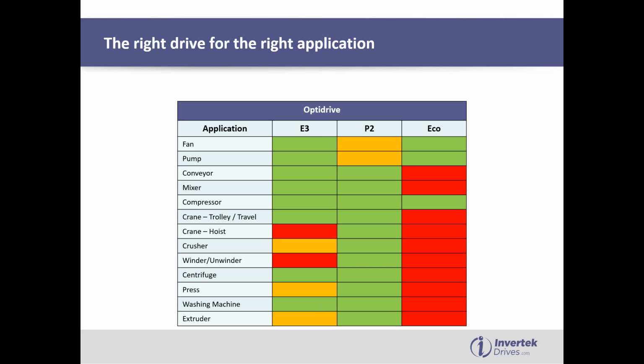So when we look at pump and fan, the biggest application area for VFDs, our E3 product is ideally suited for that application, and our Eco is specifically designed for the pump, fan, or HVAC type market. It doesn't mean that we can't do pump and fan with a P2. We can, but the Eco is designed for that space. Conveyor applications are another huge area for VFD applications. The E3 and the P2 are ideal for those, but the Eco is not suitable for conveyors, those kind of constant torque type applications.